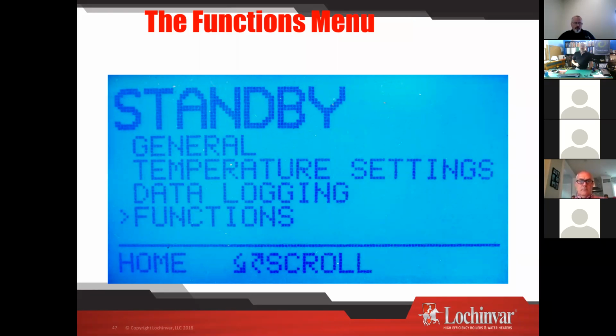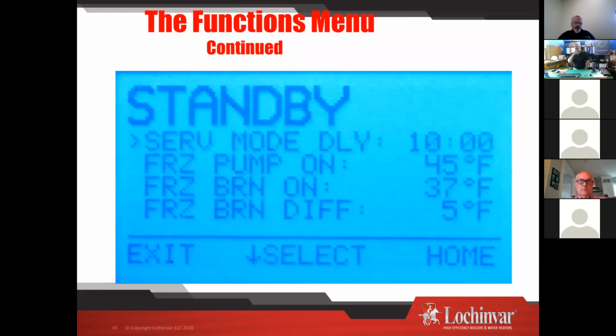All right, so I got a little bit about some functions in here. Not a lot in functions, but we really talk about our service mode delay and our freeze protection. What this is showing us is at 45-degree water temperature in the boiler, it's going to go into freeze protection and turn its pump on. At 37 degrees, it turns the boiler on, and it's going to operate a 5-degree differential. Okay, so that's where that boiler is going to operate in.